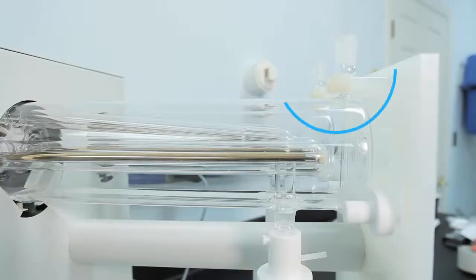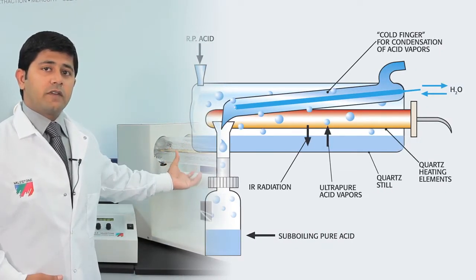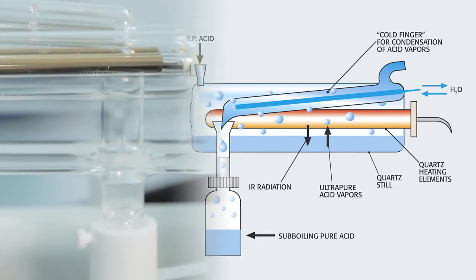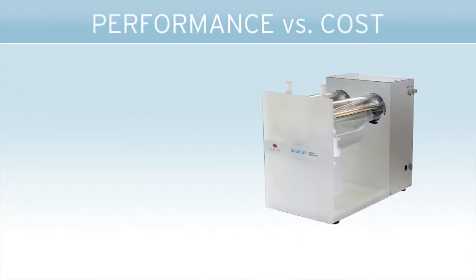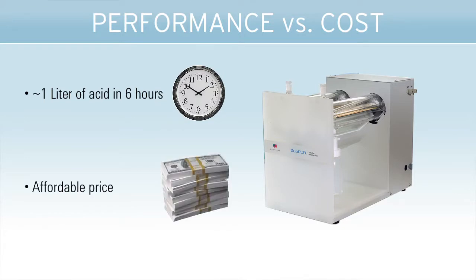The DuoPure has two quartz stills that purify the acid using sub-boiling distillation. The only difference between the SubPure and the DuoPure is that the SubPure has only one quartz still. Reagent grade acid is added here, collected at the bottom of the quartz still, and then heated using an infrared lamp. All the acid vapors from the bottom of the quartz still are collected on a cold finger inside the quartz, and then the purified acid is collected in the PFA bottle here. Because the temperature of the acid never goes above the boiling point, we only get purified acid vapors collected on the cold finger. The DuoPure can produce a liter of high purity acid in about six hours at a price that is affordable for ICP-OES users, and it can also be used for microwave digestion.